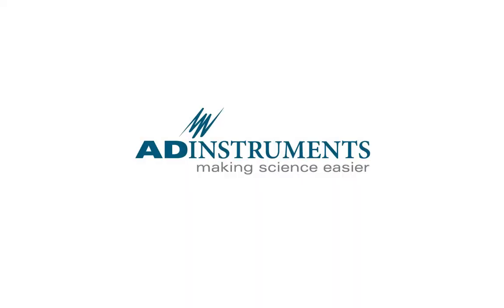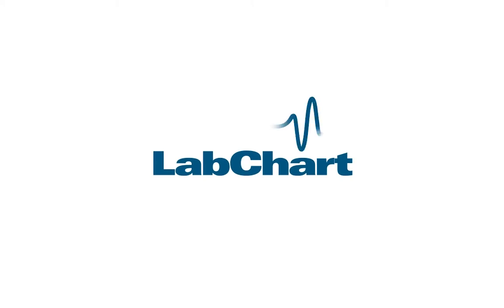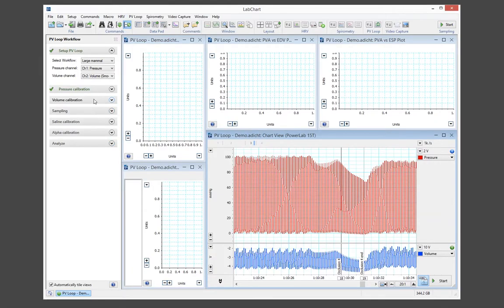I'm Amy, and today I'm going to show you a new calibration method available in the LabChart PV loop module for those of you with an echocardiogram. LabChart already offers supporting workflows to help with PV loop conductance calibration, but with this update, you can now choose to use known volume values from your echocardiogram to calibrate the volume channel in PV loop as well.